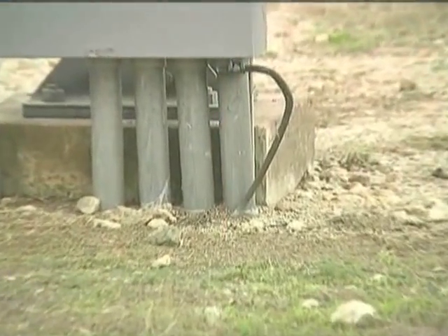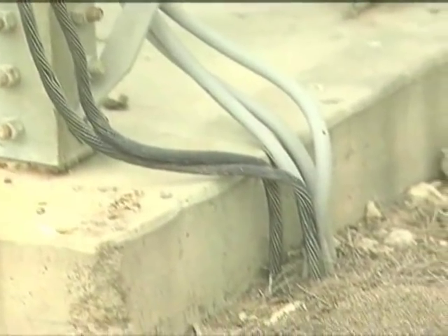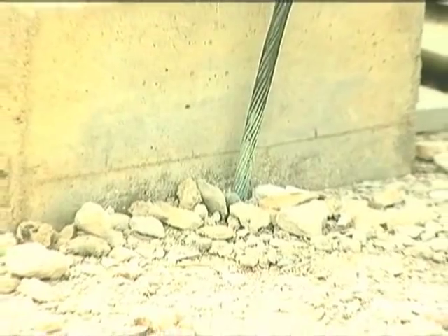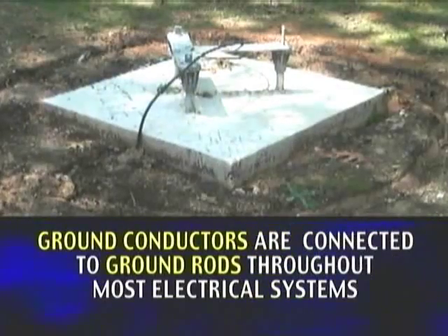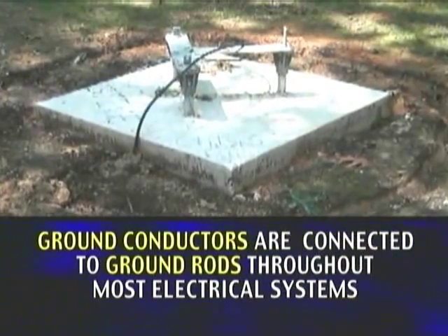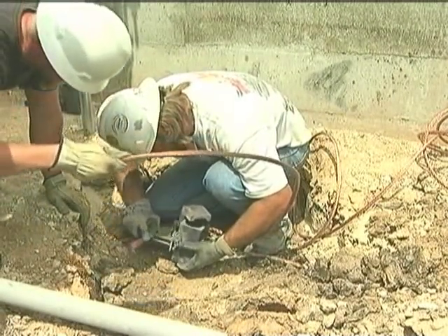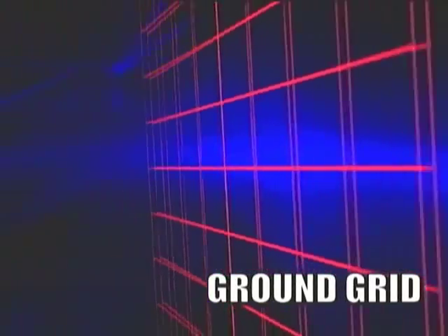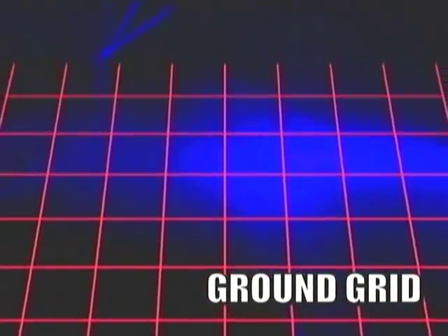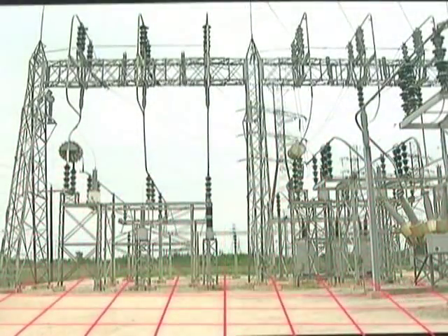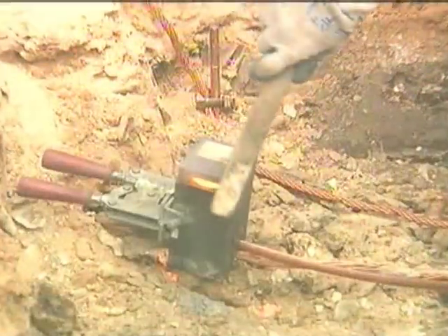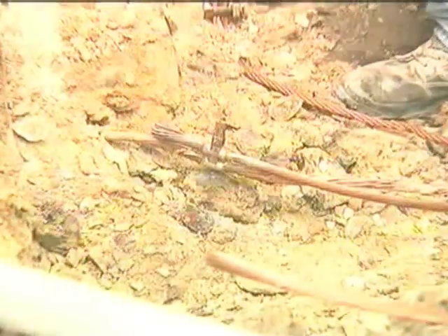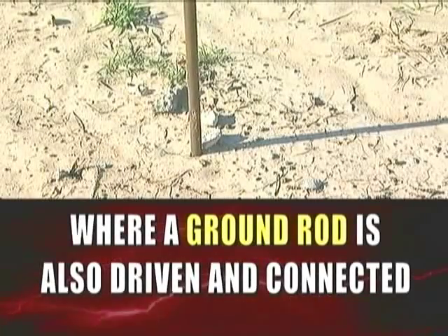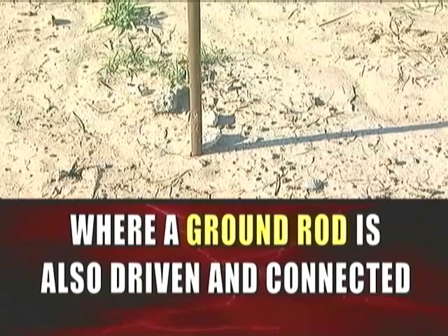Ground or grounded parts are connected to the earth or to some conducting body which serves in place of the earth. Ground conductors are connected to ground rods throughout most electrical systems and to the ground grid system inside substations. A ground grid is a system of crisscrossing conductors inside the substation just below the surface of the earth. The conductors are welded or connected at each intersecting location where a ground rod is also driven and connected.